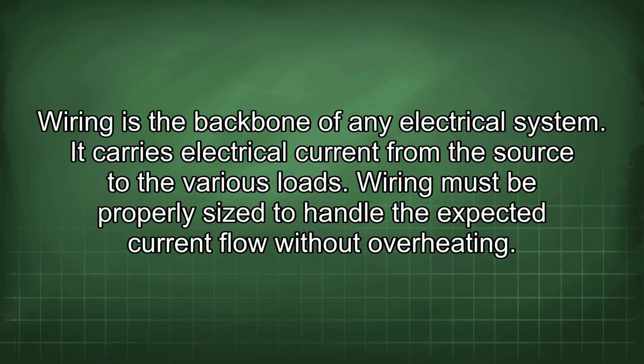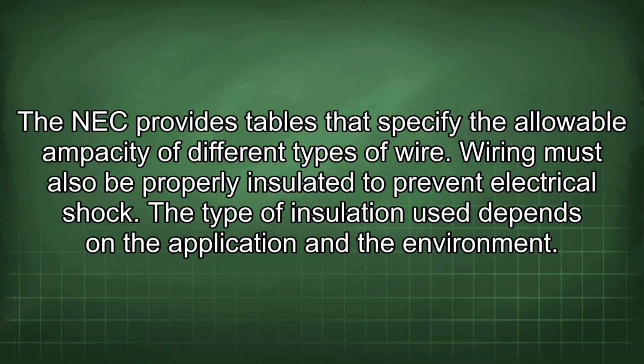Wiring is the backbone of any electrical system. It carries electrical current from the source to the various loads. Wiring must be properly sized to handle the expected current flow without overheating. The NEC provides tables that specify the allowable ampacity of different types of wire. Wiring must also be properly insulated to prevent electrical shock. The type of insulation used depends on the application and the environment.